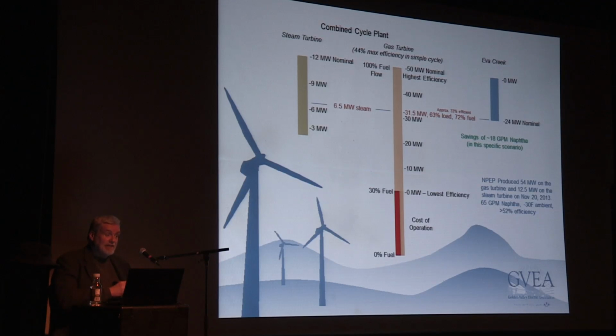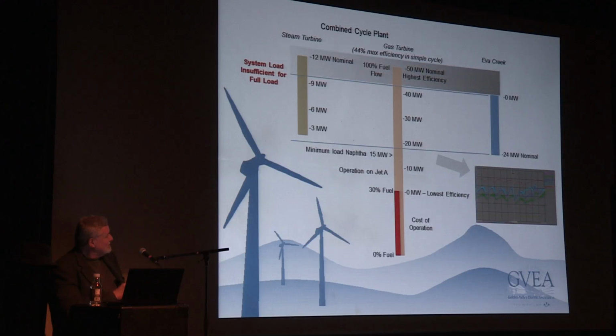And it's the same with any plant. Any combustion plant is at its maximum efficiency when it's absolutely flat out. And that's where they like to stay. They do not like to be messed with, particularly coal plants. There's a lot of expansion and contraction of the different components in there as you change the temperatures, and they work best if you just run them and leave them running for as long as they'll possibly go. When you start changing the load, they have a tendency to trip off, and once you have tripped off, you find out that some of the things that are needed to start the plant mysteriously stopped working in the last 3 months, so then you have this mad rushing around trying to figure out what's wrong and why.